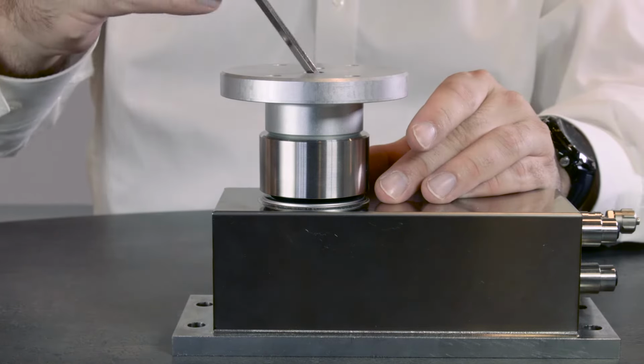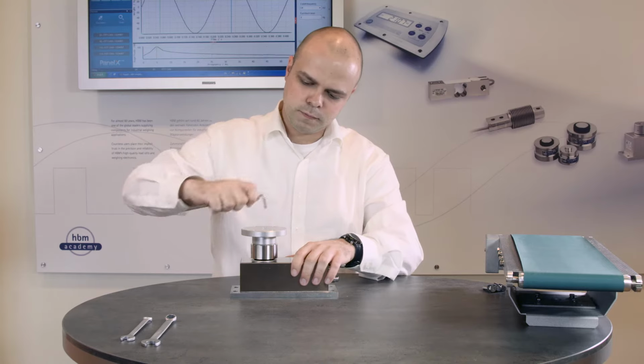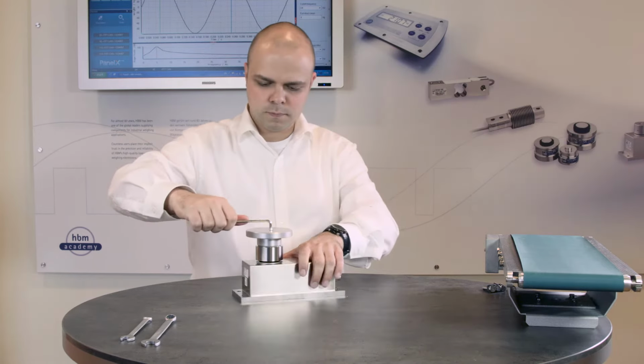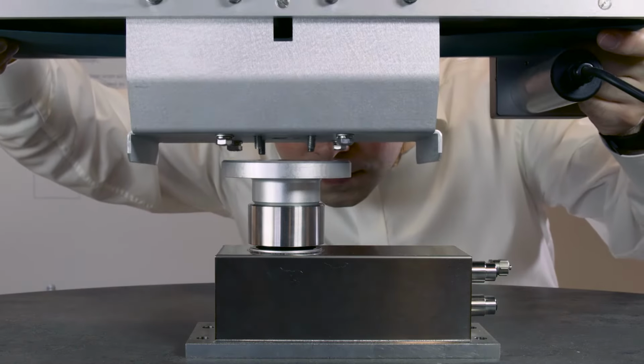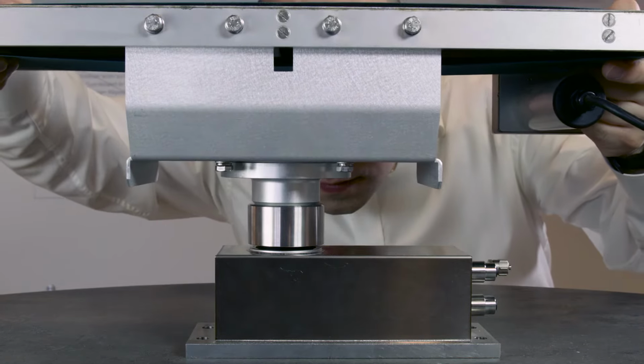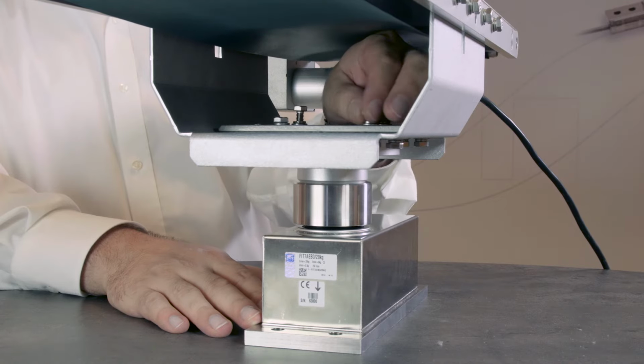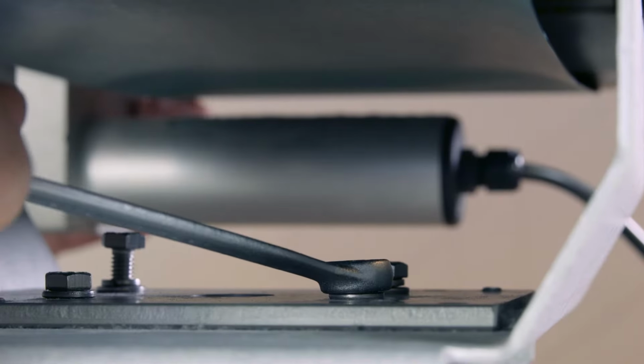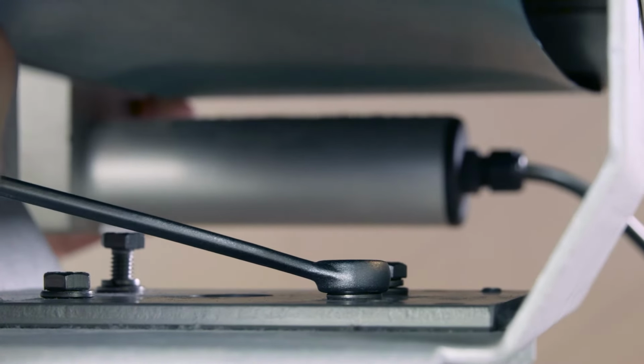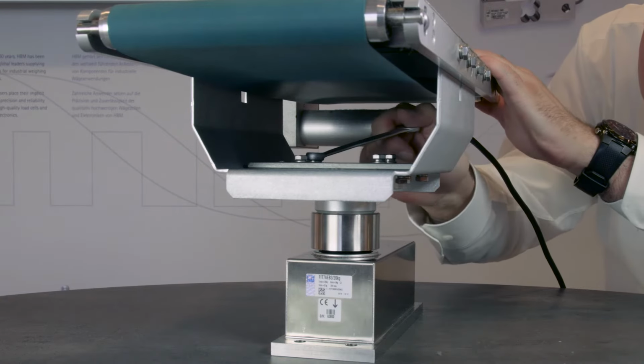Installing the load cell is easy. As a first step, mount an existing adapter part as needed. Then the load conveyor is assembled. The conveyor belt, rollers, and the drive motor are often responsible for most of the interference in the weighing signal. Less interference means more accuracy and shorter weighing cycles.